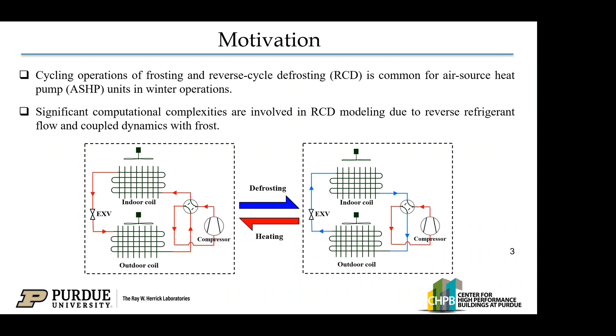Frost accumulation is a common phenomenon for cold climate heat pumps, and a periodic system needs defrost to return to its operating characteristics. The operating nature of a cold climate heat pump is this cycling operation between frosting and defrosting. Modeling this process is challenging because you have the coupled dynamics of refrigerant, frost, and defrost. So the goal of this work is to fill a gap in the literature: there is no general simulation tool that can handle the cycling behavior of frosting and defrosting.